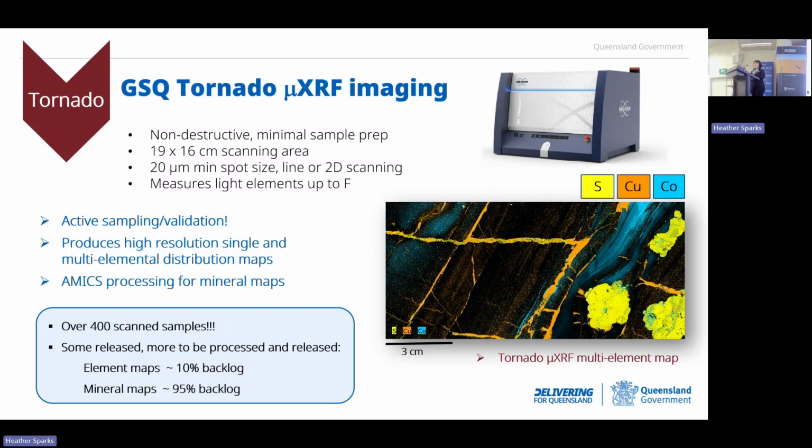Well, the next instrument is probably our pride: we have our own Tornado instrument, and it was really, really well used. It's not a destructive method. It requires relatively minimal preparation, though some polishing is still needed. It can scan quite large samples, up to probably 19 centimeters long. It has quite a reasonable resolution down to 20 microns, and a good range of elements.